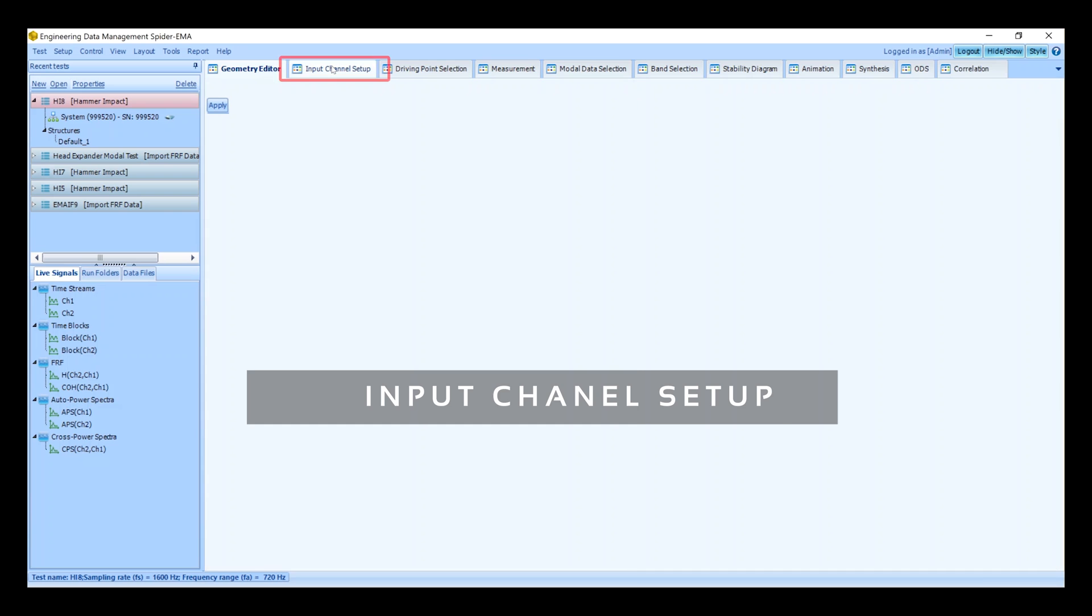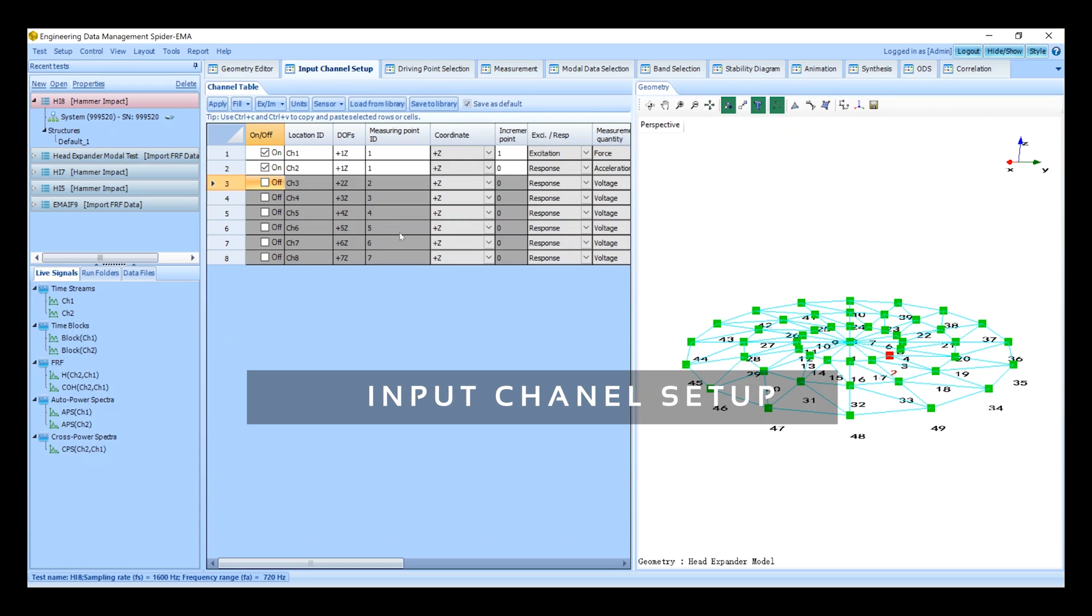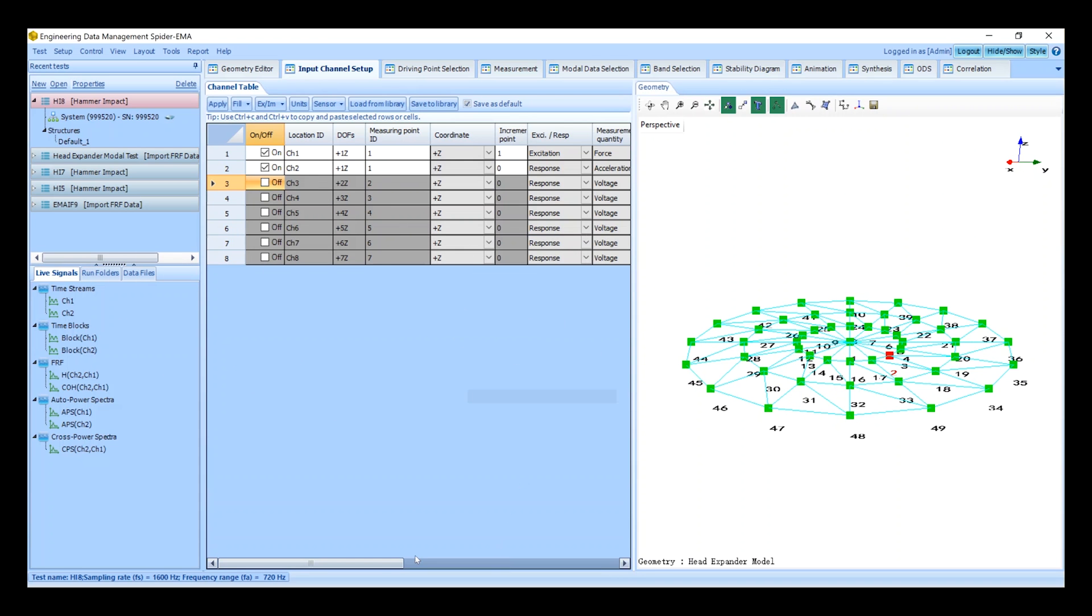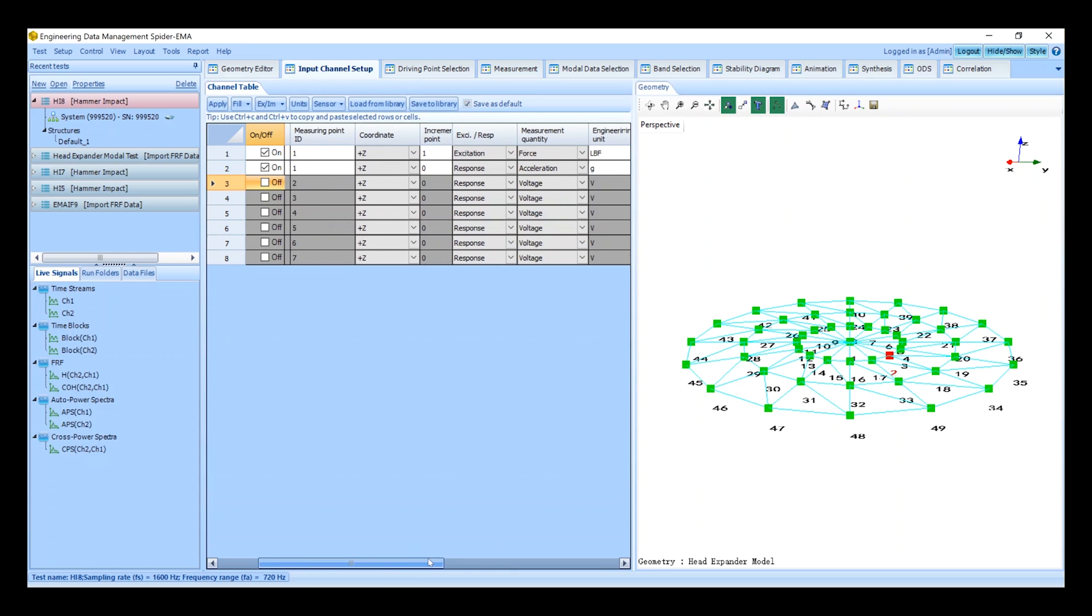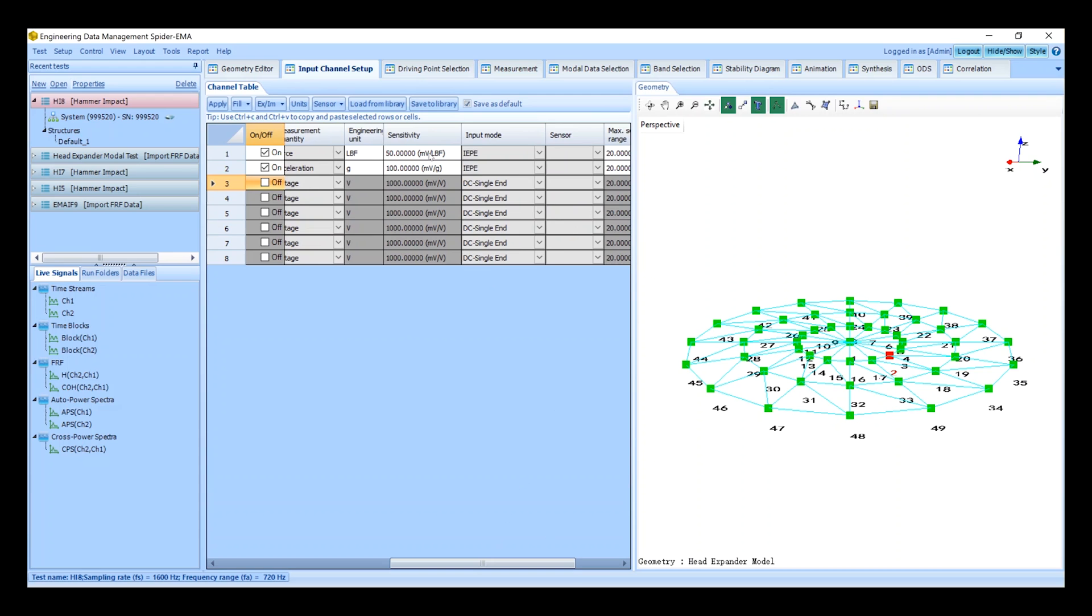First enable the input channels using the checkboxes. Here we will only be using two channels so we'll disable the others. Set the sensor sensitivities for each channel as well as the measurement units and input modes.